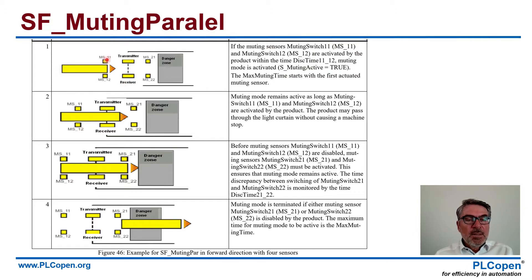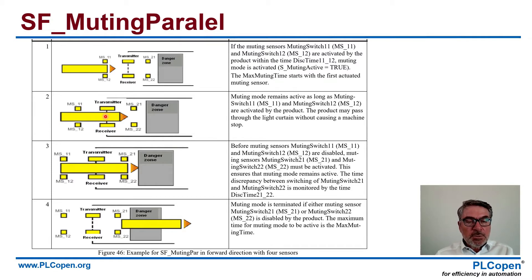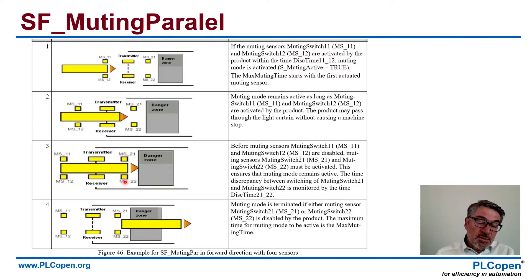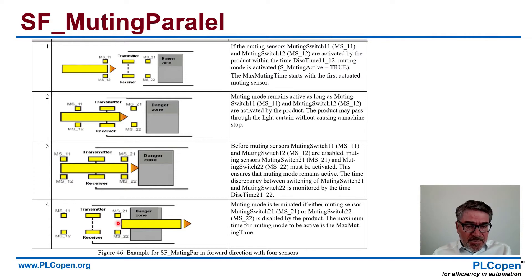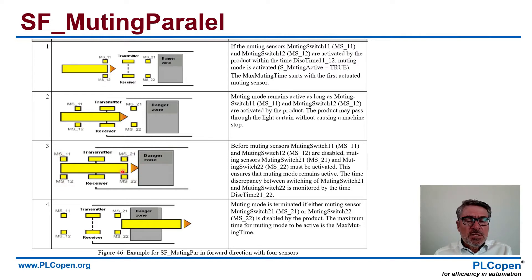Look at parallel muting. For parallel muting, we have two sets of sensors, and this is the light curtain — that is the safety functionality that we want to mute, to suppress. So the car body gets in, it blocks the first two sensors, and there can be a time difference: it can be the first one and then two, and there is a little discrepancy time that we check. Then it moves in through the light curtain, which is still okay because it's not in a danger zone. And before it exits, it unblocks those two sensors and blocks the second pair of sensors. Also there, it can block the first one a little bit faster than the second one, so we want a time discrepancy and a time evaluation about the whole trajectory of moving in. These are all checkpoints for us. Then it can go out and unblock those sensors. We know that it is the right product — the car body — and it enters the danger zone. So the positioning of these sensors is crucial.